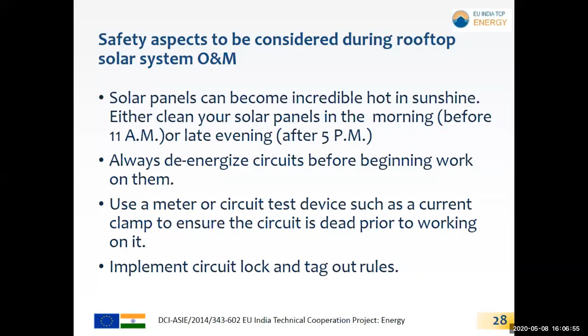Inverters have a large number of capacitors that could hold a charge even after the power source is removed. So wait at least 10 minutes to allow a full discharge of the internal capacitors, or you can follow the manufacturer's guidelines. Then, no socket outputs are permitted from the inverter output.